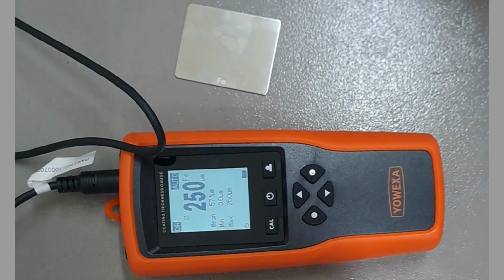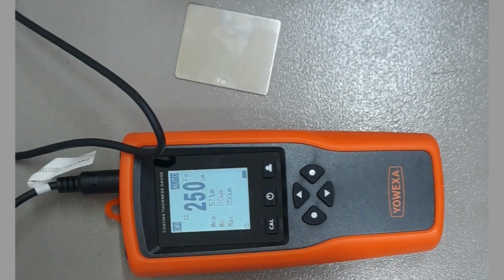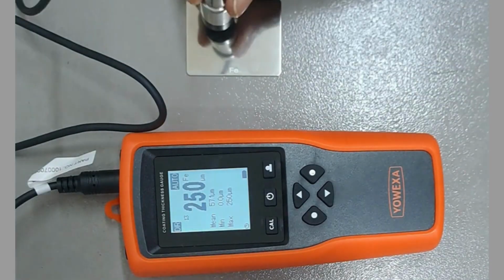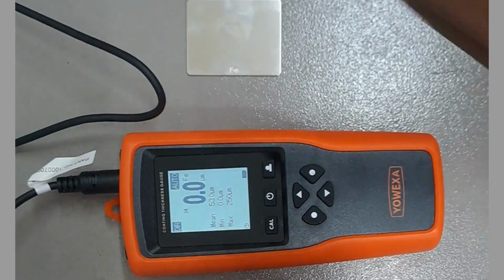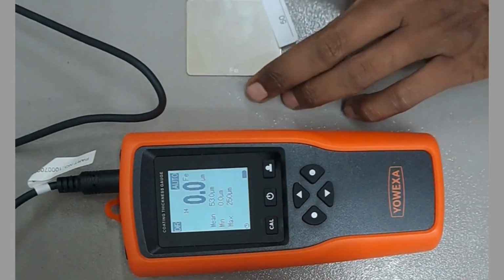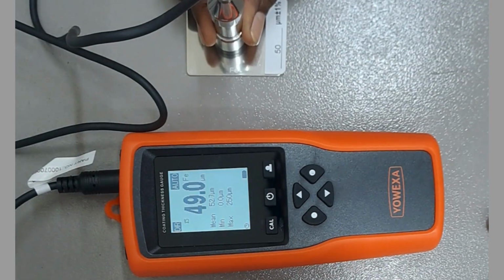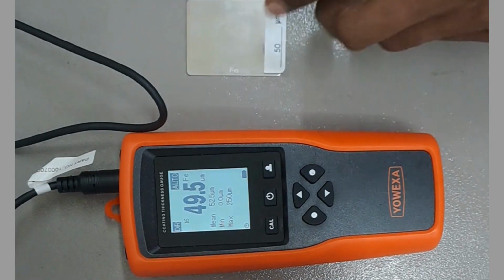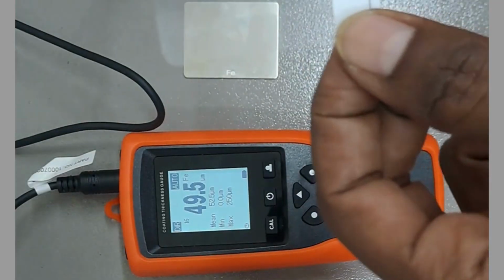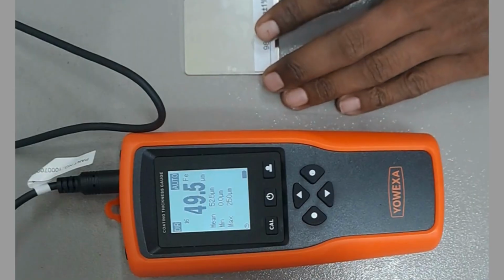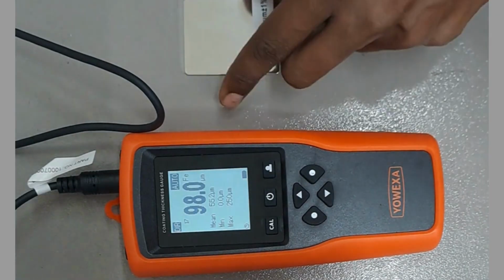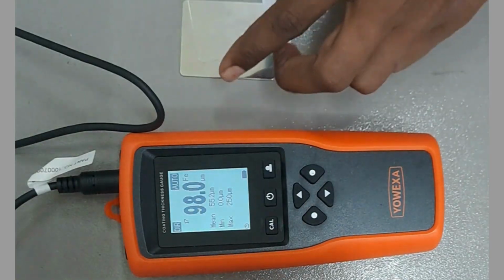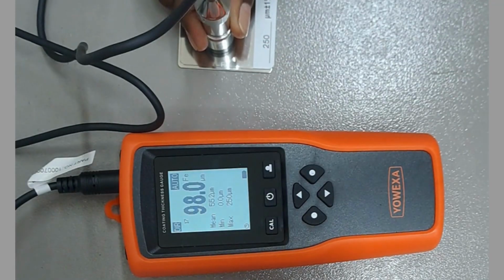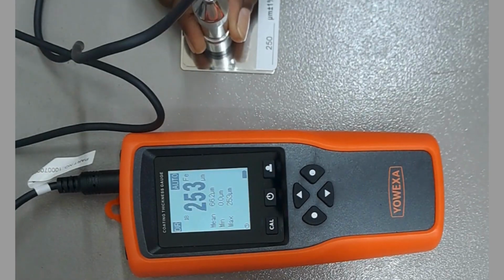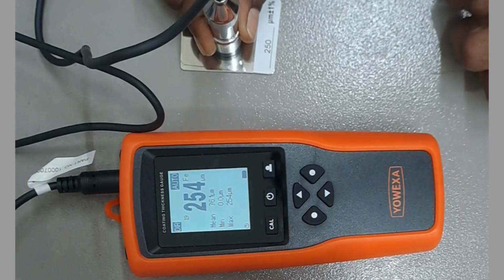Okay. Now we will verify the foil one by one to ensure that the calibration we carried out is correct or not. Now we will do the zero testing. Okay, it's 0.0. We will verify the 50 micron. It's 49.0. 49.5, almost there. 98 micron. It's 98.0 exactly. And then 250. It's 253. So that's all the calibration.